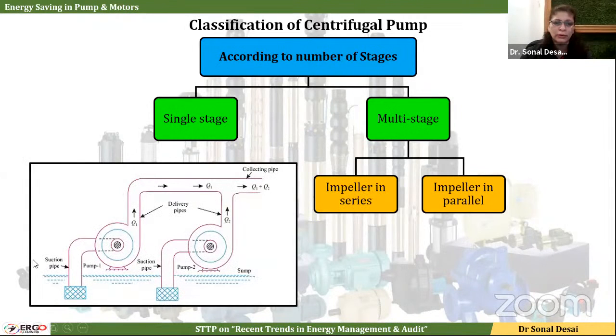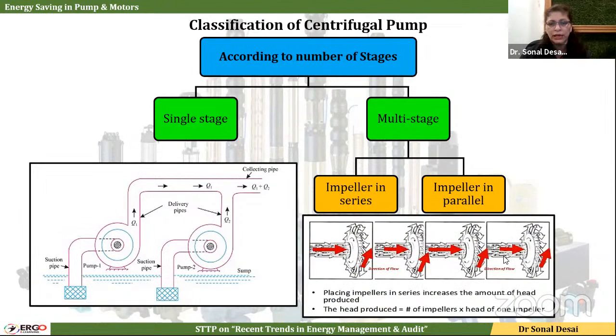Then staging is another classification, like a single stage. Here two pumps are shown in parallel to each other. Both have suction and delivery. They are mixing and then the final flow goes ahead. So that is a single stage arrangement. While in the case of a multi-stage, the outlet of one goes to the next and so on. So wherever a higher requirement is there, it can be a multi-stage arrangement.